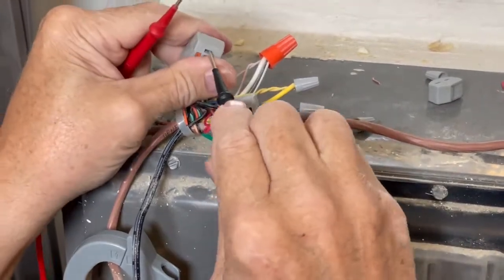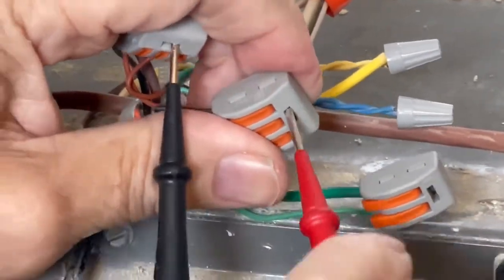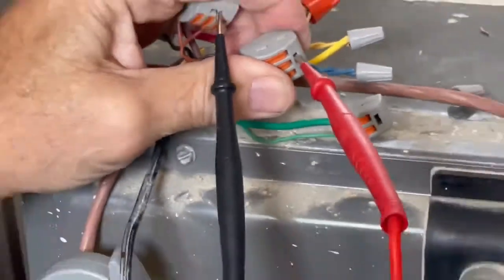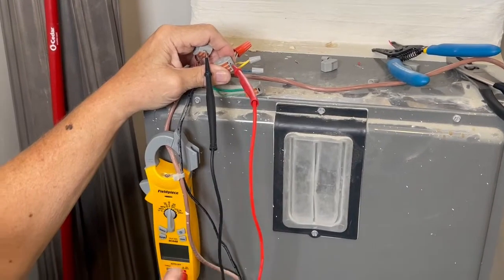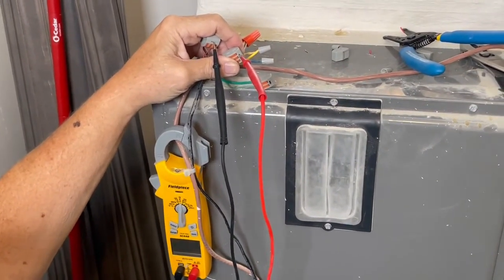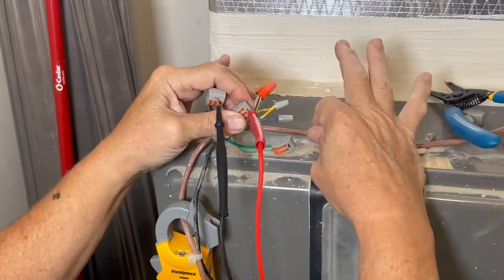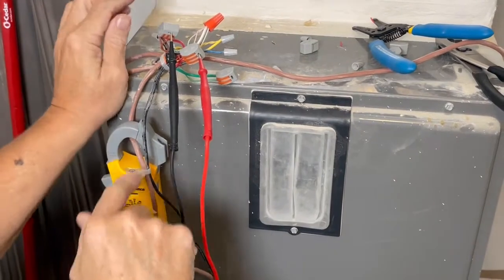It's simple — just put the lead in until it touches the metal at the back, stick it in there, and check your meter reading. Right now I've got my breaker off so we don't have any sparks flying. It's 24 volts so it doesn't actually show up, but that's exactly how you test it. You want to find out if you're getting a signal going out to your condensing unit, you do the proper wires for that.